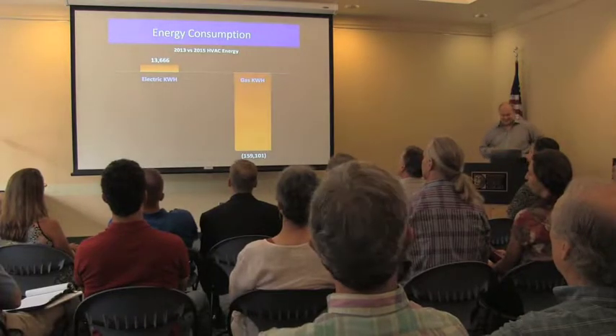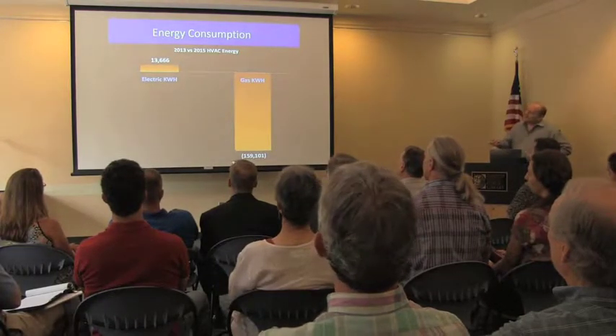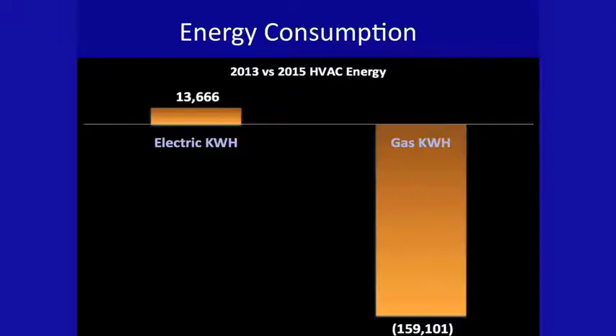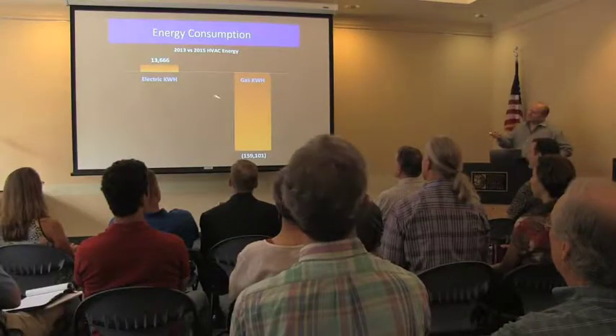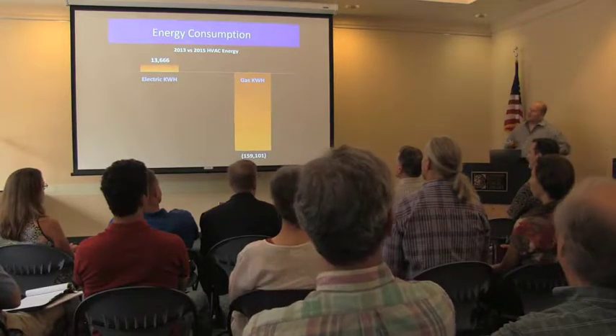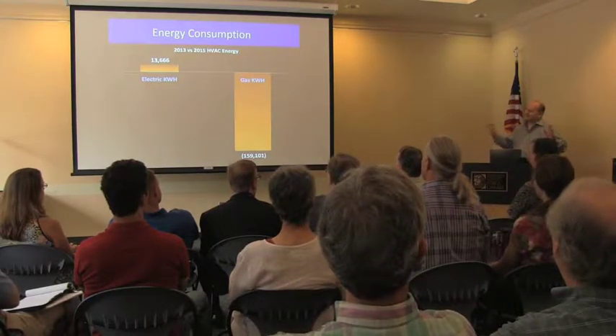So it was interesting that in that project, we cut out about 160,000 kilowatt hours of gas, and the electricity went up by 13,000. Now, this looks weird because we're essentially doing the entire gas heating for about 8.5% of energy than we did before. Now this would mean the geosystem is 1,200% more efficient. How can that be? Well, it is and it isn't.